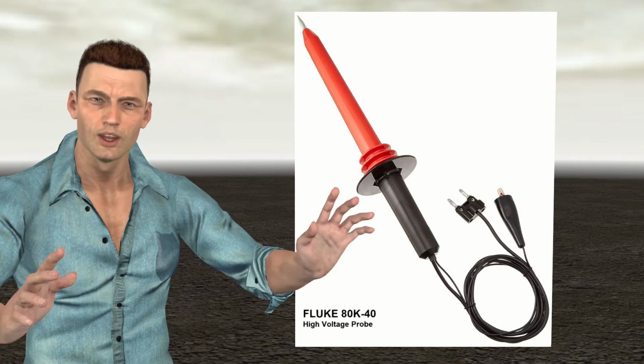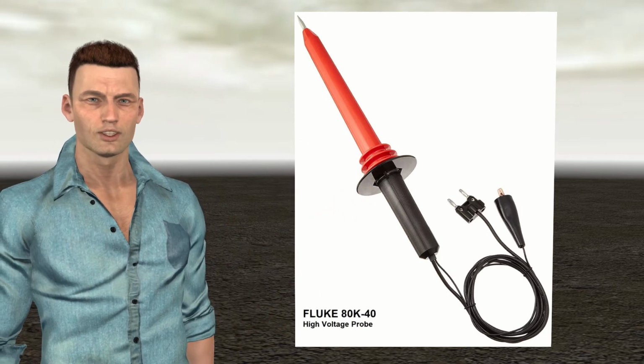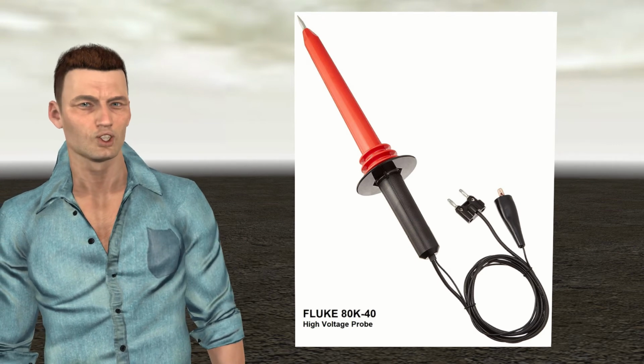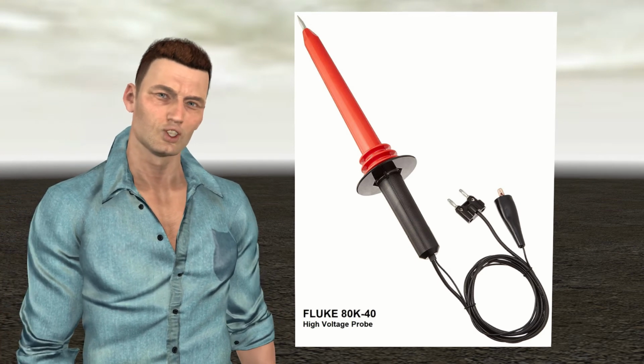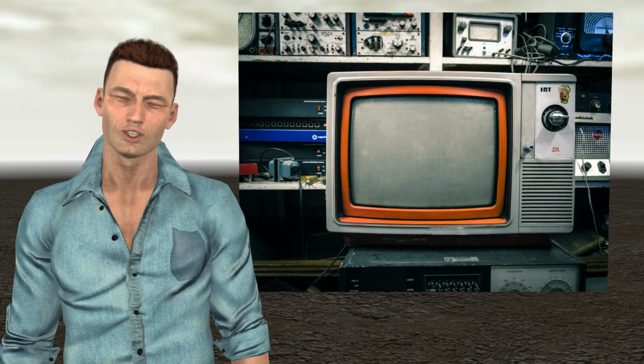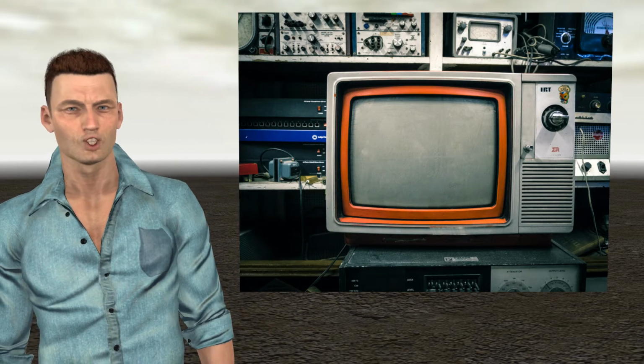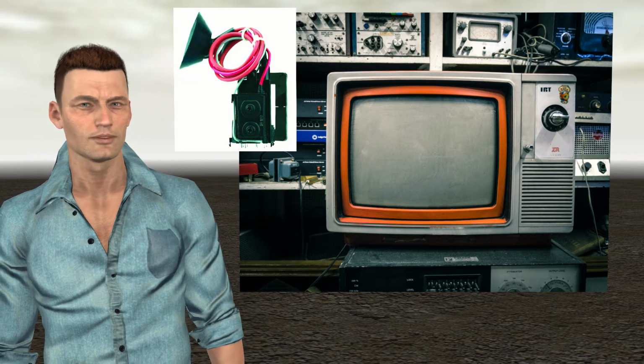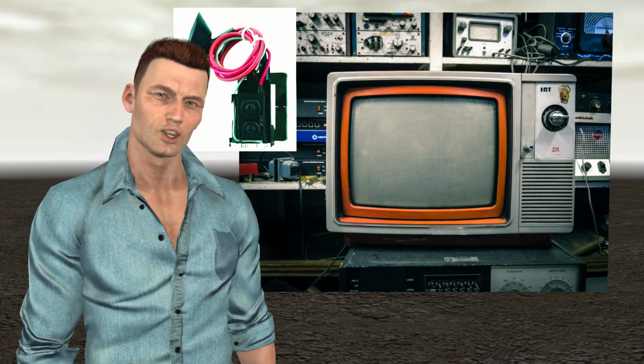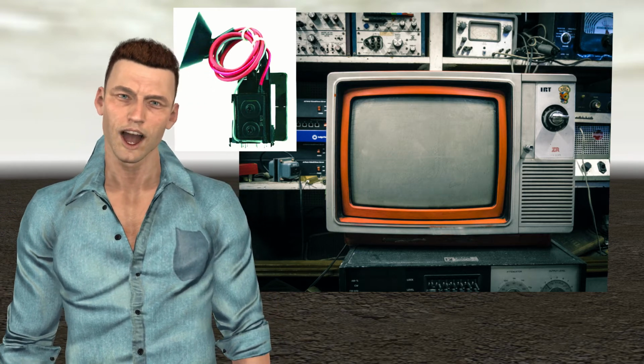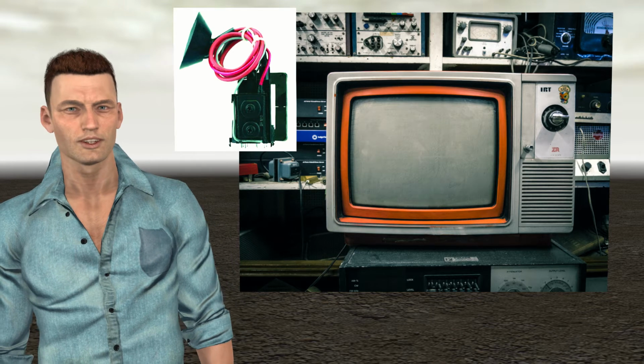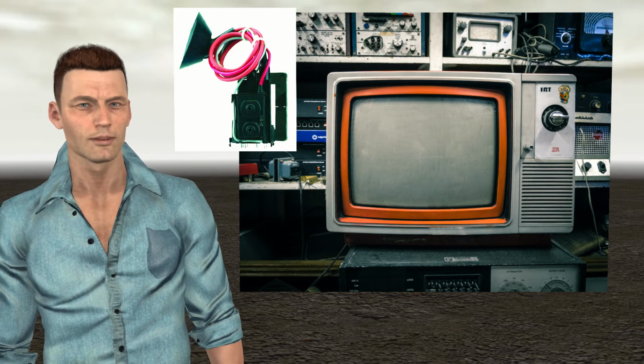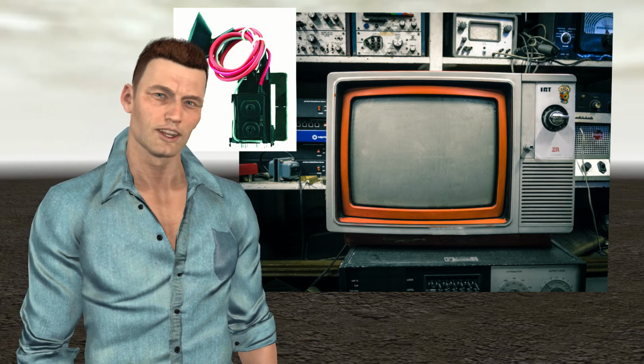This probe is valid for Category 1 systems, which implies using it in circuits with limited energy, such as in high voltage circuits used by cathode ray tube televisions with flyback type transformers, or in photocopiers, laser printers, etc. They are generally not capable of delivering very large currents. For example, in the case of flyback transformers in older televisions, they could be a couple of milliamps.